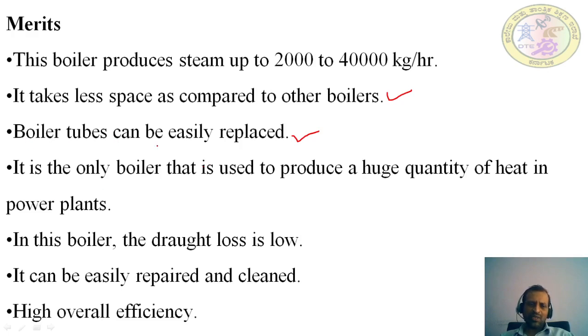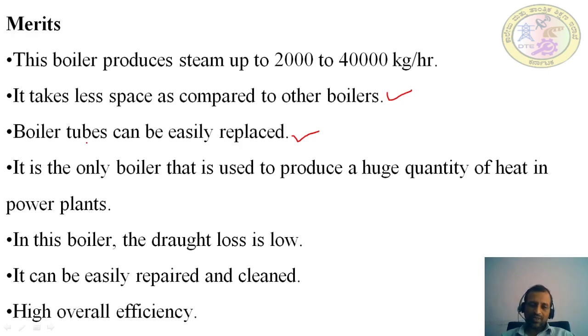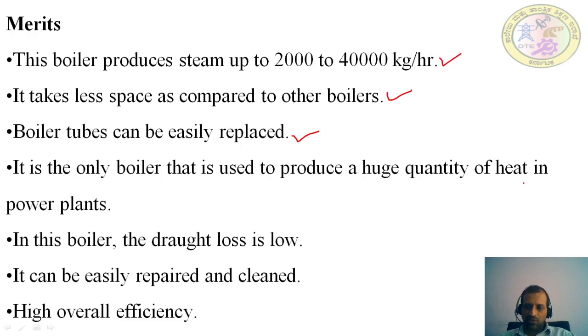The boiler tubes need replacement because impurities in the water get deposited on the walls of the water tubes, creating back pressure which can lead to explosion of the tubes. To avoid this, tubes need to be replaced periodically, or purified water should be used for steam generation. It is also the only boiler used to produce a huge quantity of heat in power plants.